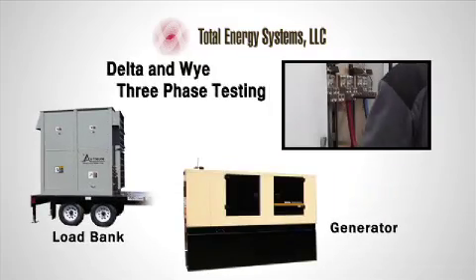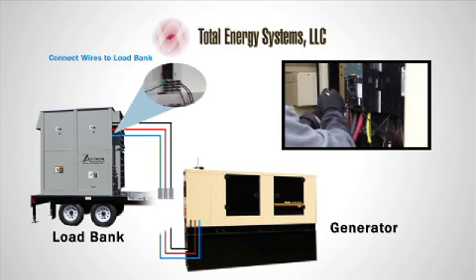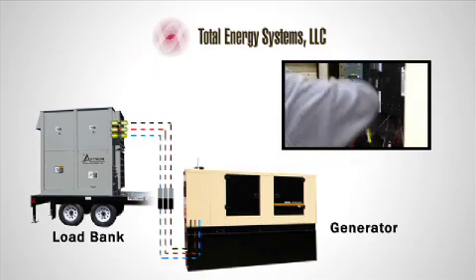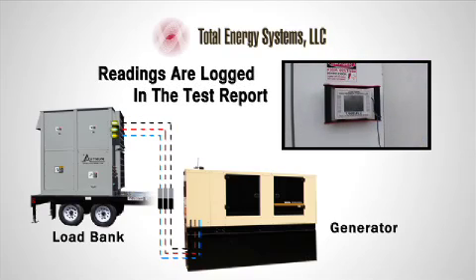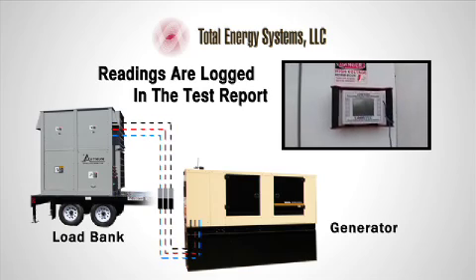Our technician first connects the wires to the load bank, then connects the wires to the generator circuit breaker. The generator set is then started, and quite often, a set that has not been loaded on prior runs will smoke on start. The technician records the readings, verifies the set is performing as it is meant to, and logs it in the report, referencing the hours that have passed.